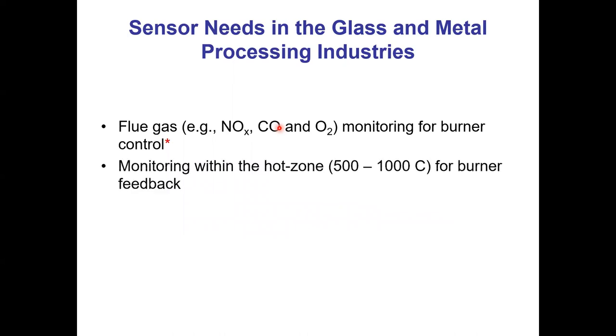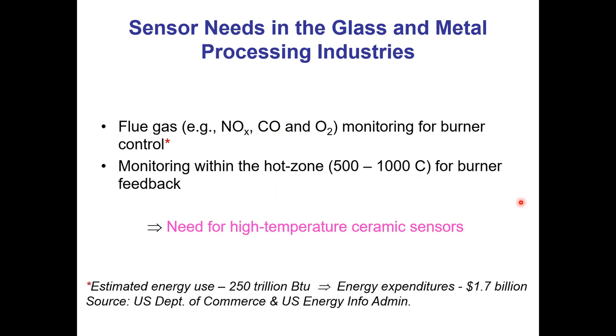There are needs for gas sensors in glass and metal processing industries. You're trying to detect flue gases — species like NOx, CO, and hydrocarbons — and monitor emissions burner by burner in a glass melting furnace or commercial-scale metal heat treating furnaces. The monitoring environment is harsh; the temperature range is anywhere from 500 to 1,000 degrees Celsius at the burner. You need high-temperature ceramic sensors for this kind of application, and the Department of Energy is interested because these are very energy-intensive processes.